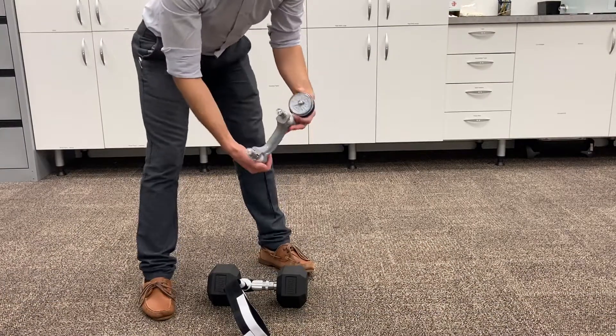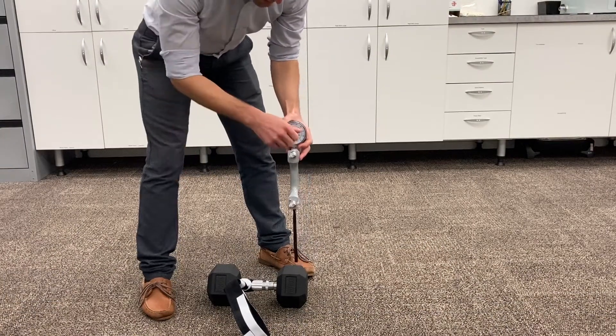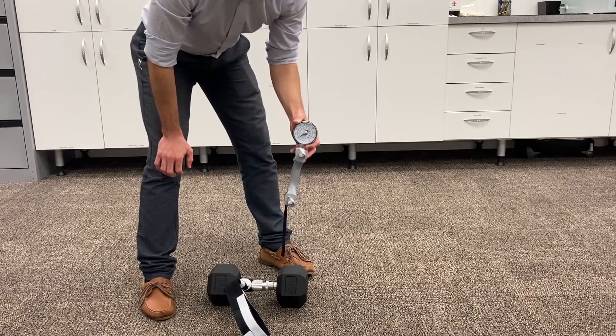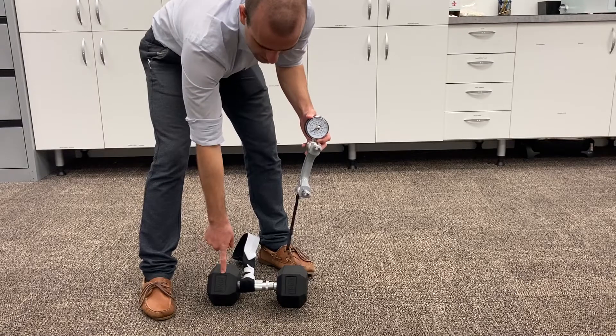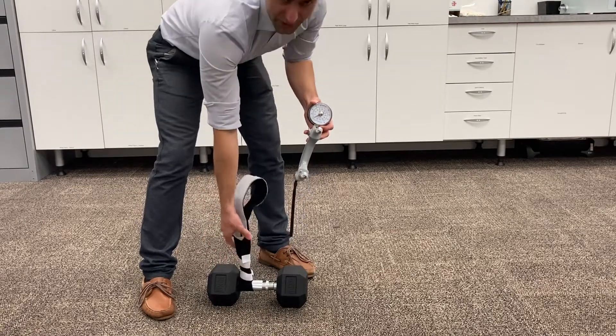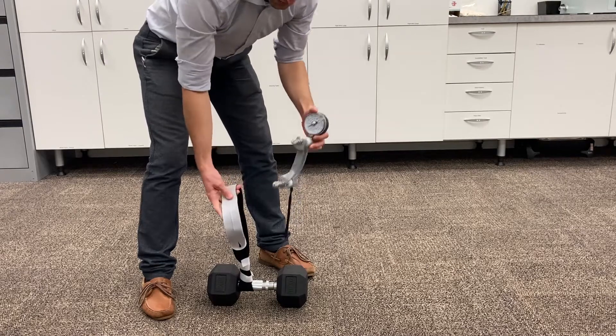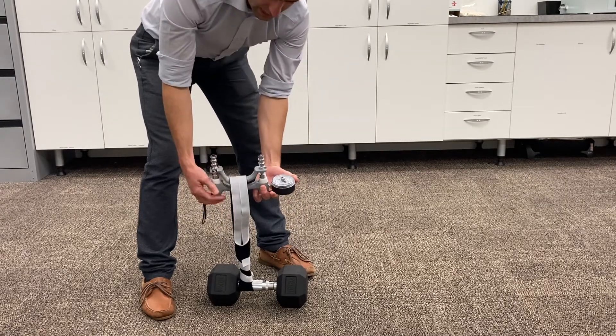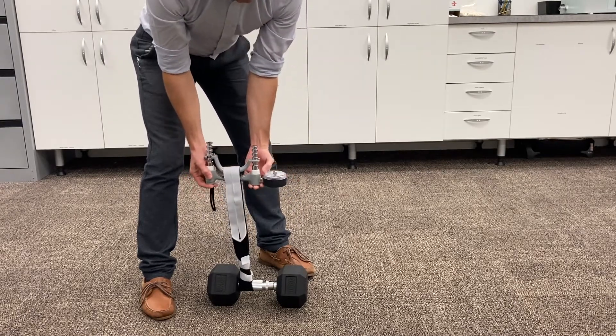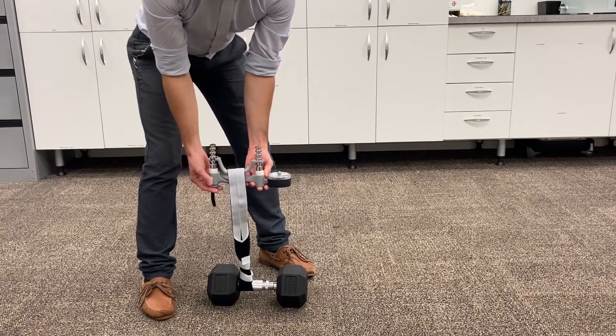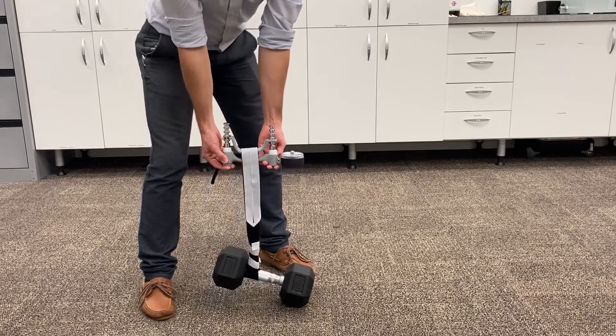We've got the handheld dynamometer here which is recording zero. We'll test it against a known weight, in this case it's a 10 kg dumbbell, and what we created was a loop that allows us to attach it to the weight as well as hook the handheld dynamometer on it. So we want to keep the two poles vertical and make sure that when we lift up the handheld dynamometer...